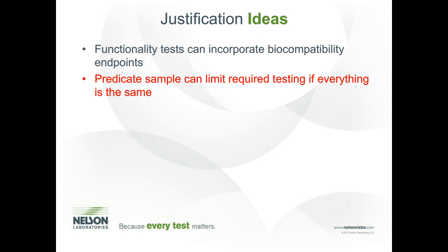But we talked about a predicate sample. When I say predicate, I really mean your device that you manufacture. I know that we look at 510Ks or some of these test predicates, we're looking for something on the market known to be safe. But when we're looking at justifying out a biological endpoint, we're talking about a device that you know intimately. You know where the supply of the material comes from. You know the processing, because those are the kind of answers that we need to justify out a test.